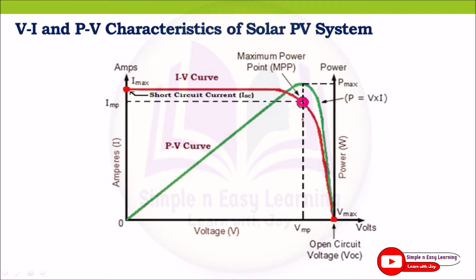The voltage corresponding to the maximum power point is called VMP (voltage at maximum power point) and the corresponding current is IMP (current at maximum power point). These readings are needed to find the fill factor. The rated VMP lies between 75 to 90 percent of open circuit voltage, and IMP is 85 to 95 percent of short circuit current.